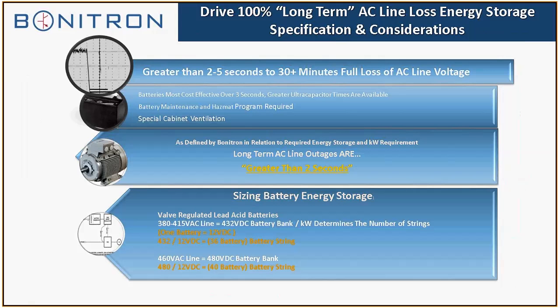Long-term outage, or battery ride-through, greater than 5 seconds. Now there's an update to this, and we say 30 minutes plus. Well, that just means we can do any amount of time, but you have to keep in mind that the higher the time, the more the batteries, the more expensive the solution, with energy storage being the most, or at least half, of the cost of the total ride-through solution.